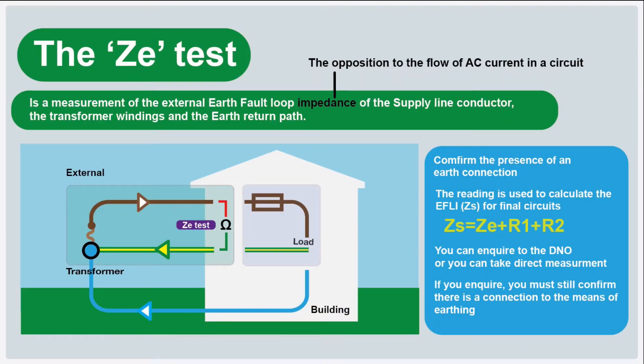The ZE test is an important test. It's a measurement of the external earth fault loop impedance of the supply line conductor, the transformer windings, and the earth return path. ZE stands for Z (impedance) E (external) — external to the building. So we have our house with our fuse board and our electrical installation, and we're testing the incoming supply line and the earth return path.